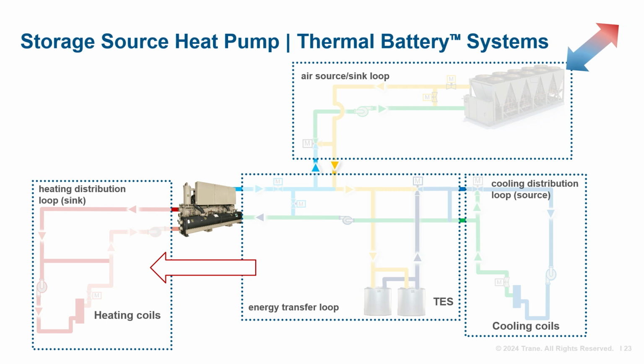The thermal energy storage tanks can collect energy from either the air-to-water heat pump, the building when we're cooling with ice, or both, with their capacity controlled by the building automation system. The building automation system also coordinates airside economizer operation so as not to waste beneficial energy now if needed later. Operating modes from the distribution loop perspective include cooling only, heating only, and simultaneous heating and cooling. This system is flexible and offers an electrified heating solution even in cold climates.